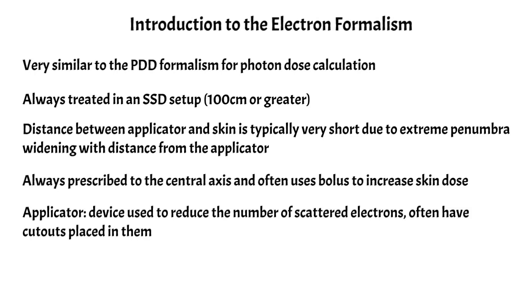The applicator is just a device used to reduce the number of scattered electrons, and they often have cutouts placed in them. So a cutout is basically the electron equivalent of a blocked field. You'll place it into the applicator, and that's what you'll use to define some of your dose calculation parameters.